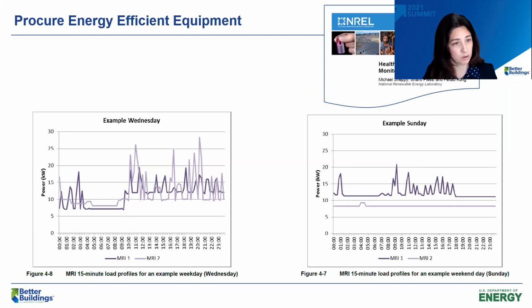So let's see, in 2016, NREL published a research paper, Healthcare Energy End Use Monitoring. And here are two graphs from this paper. I think you all are very aware that some of your process loads for your medical equipment are pretty high energy consumers. In these graphs, there are two MRI machines, and this is the load profile over 24 hours. You can see on Wednesday, there's a base load of about 7 kilowatts for an MRI machine, and then it's in use some of the other time. But look over at Sunday. One of the MRI machines is not really used the entire day.